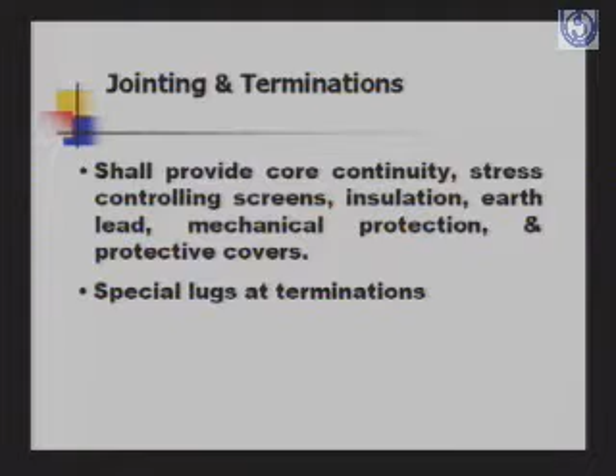They require special lugs at terminations. The joints and terminations can be of various types. Earlier we were using cast iron molded joints and terminations, but now these have become obsolete and have been replaced by epoxy resin type, heat shrinkable type, cold shrinkable type and push on type joints and terminations for cables.